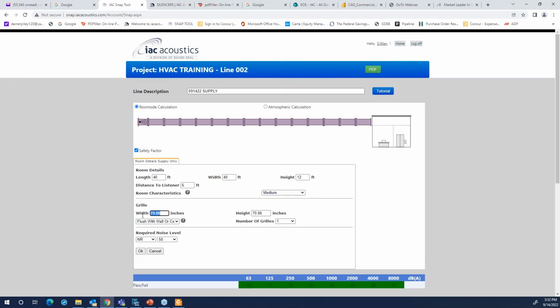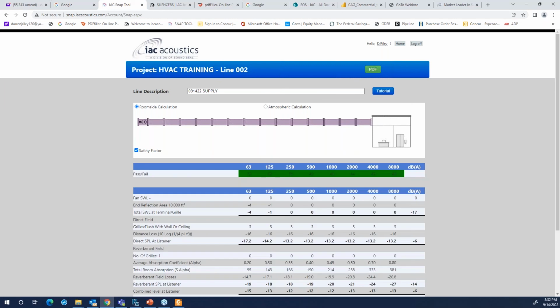All right, so we'll change this. For this one here, we'll use 40 by 36. You can do an NR level, you can do an NC level, or you can do a dBA level. We'll do an NC level here, and let's set this up for a college dorm room or a nice, quiet office space. We'll set it for 35. Click OK, and you are now set with your parameters, which is great.